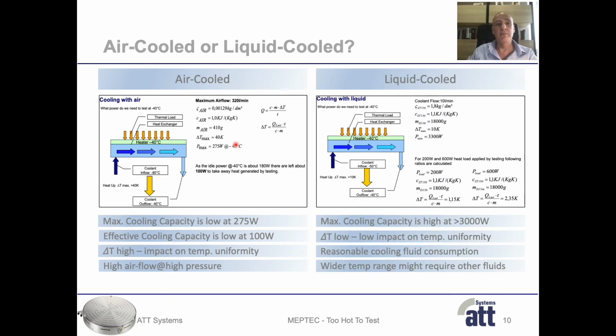So how does this compare with a liquid-cooled system? The heat dissipation process is basically the same, but if we look at the properties of the thermal fluid, then we can realize that the density is much higher compared to air. And higher densities basically mean that we can transfer larger amounts of energy. And this is the main reason why liquid-cooled systems have a significantly higher cooling capacity or cooling power compared to air-cooled systems.